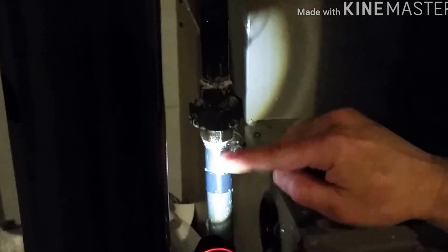It's a very faint leak, but that's how you find them. The rest of this you don't see any other bubbles, but this one keeps growing down here. So obviously where this union is connecting to the black pipe is where the leak is.